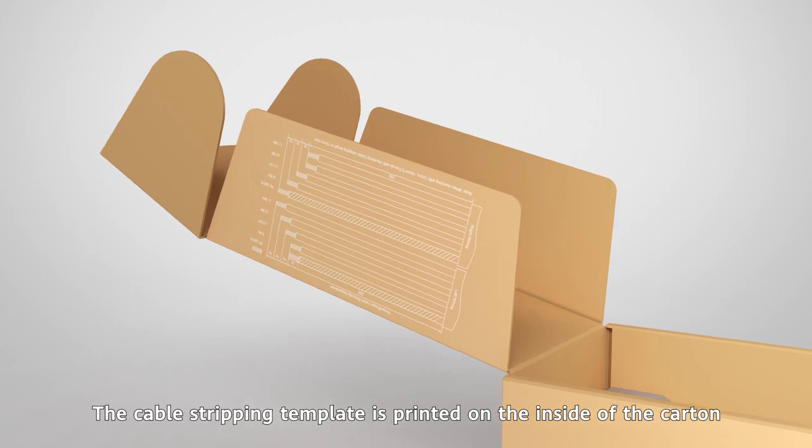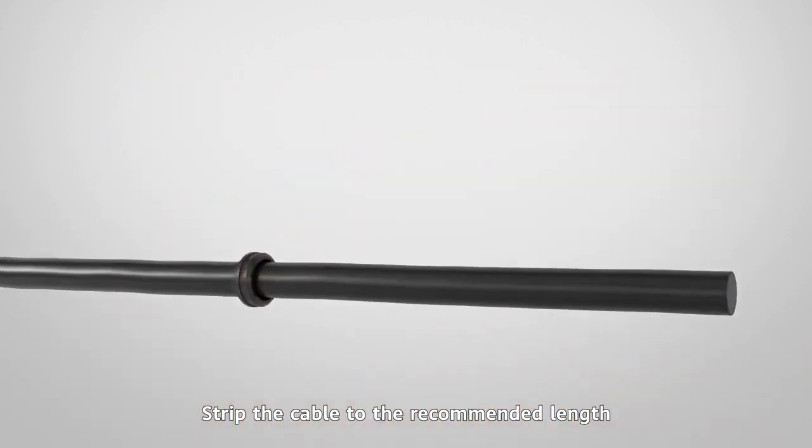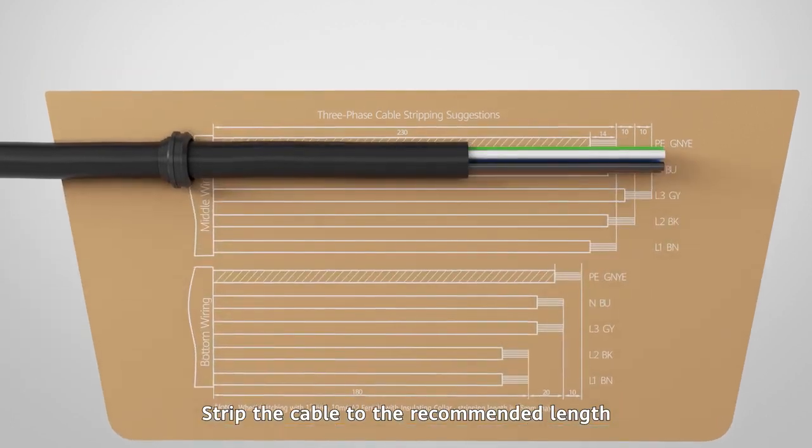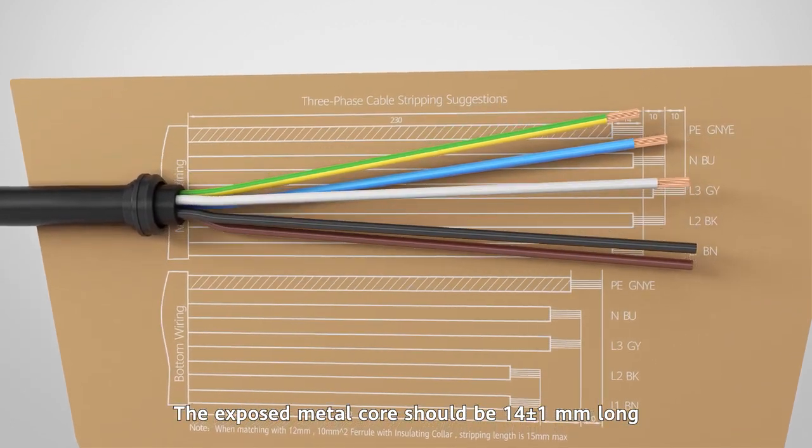The cable stripping template is printed on the inside of the carton. Strip the cable to the recommended length. The exposed metal core should be 14 plus minus 1 millimeters long.